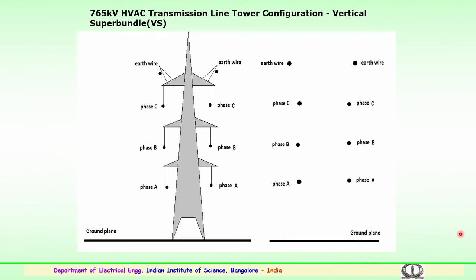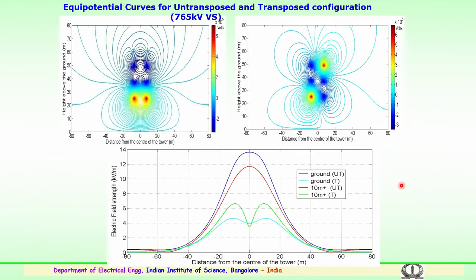So this is again a typical 765 kV transmission line tower configuration for a vertical super bundle. You can see two circuits here, ABC and again ABC, and you have two earth wires for lightning, and the tower schematic here. This is the ground plane. Intentionally the earth wires are connected here, and you see the ABC phases are changed. That is, a proper transposition is done so that transmission is better, and also the electric and magnetic fields are reduced to a certain extent in case of the conductor carrying more current. So these are some of the magnetic field and electric field values which have been simulated using developed software.